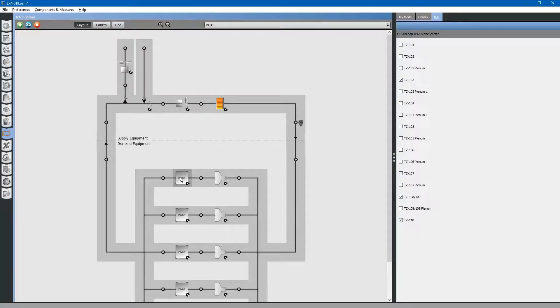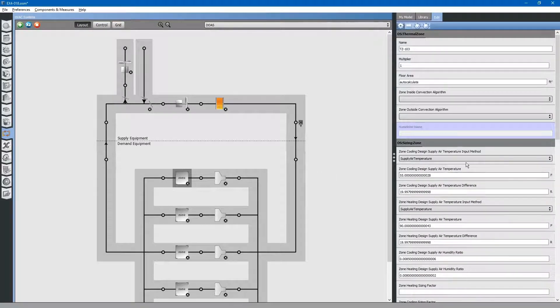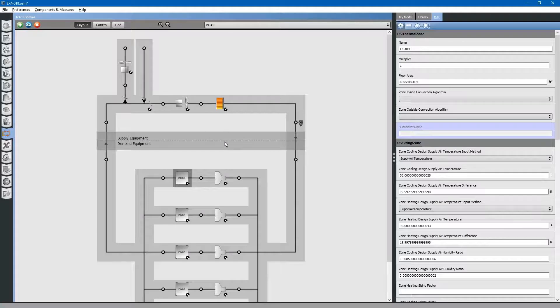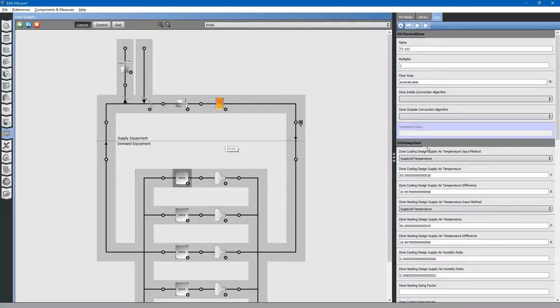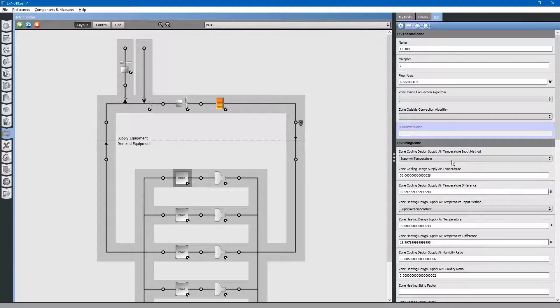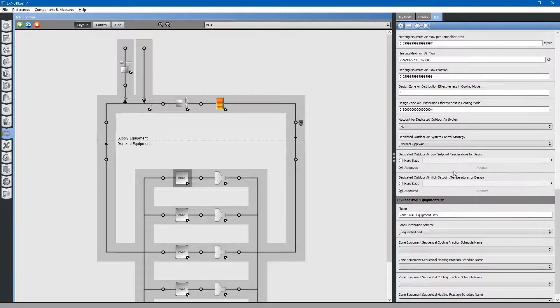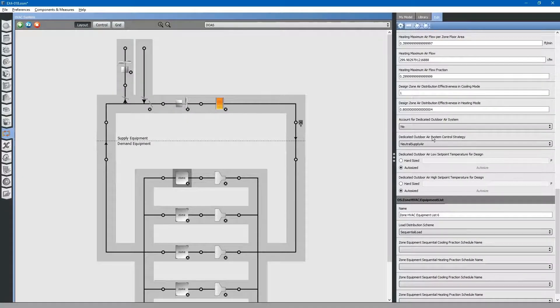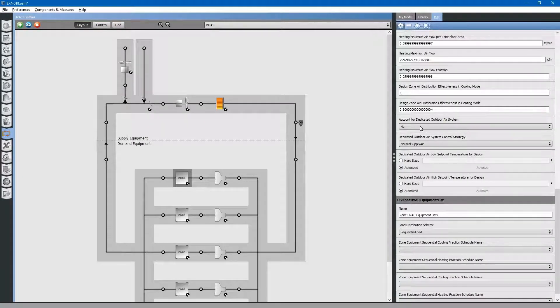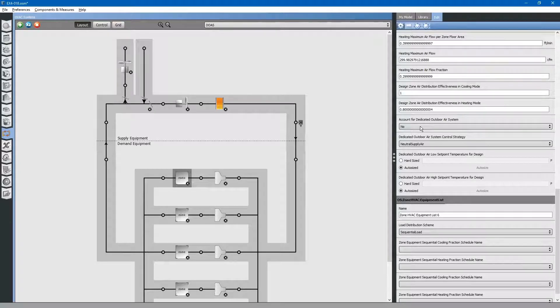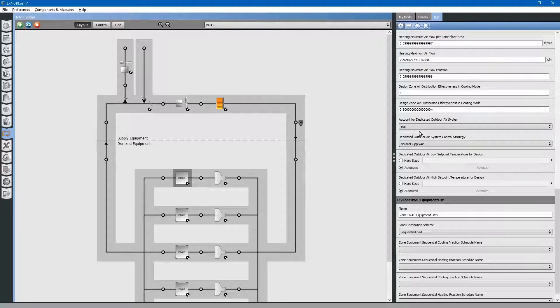Next, let us select the zones, starting with this zone at the top. Most of this information is populated from the main supply air system. We do not have to worry about zone sizing. You would only use this if you had VAV boxes. But we do want to scroll down and click the drop down for account for dedicated outdoor air system. We will select yes for this.